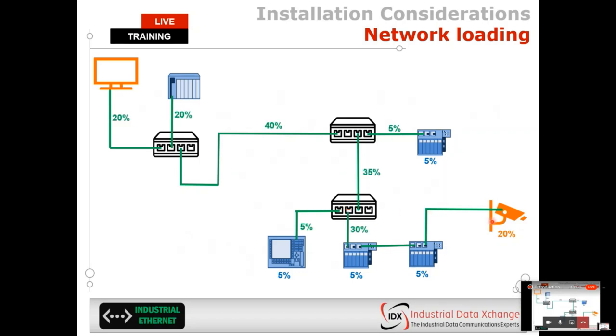In this application, I have a 20% net load coming from my video camera. It's quite busy because it's got a massive UDP telegram of 1500 bytes of video data - it's in full HD at the moment. Each of my IO stations only applies a 5% loading, so I add these three loads together, meaning this port is getting a 30% load. Another 5% port loading is added by my HMI, which means this port, linking all four network components, has a 35% net loading on it.